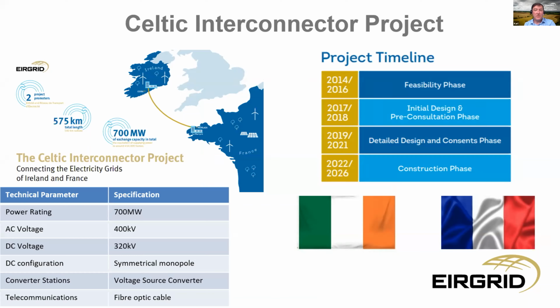The specification of the project is similar to that of EWIC. It will be a VSC converter with newer technology. It will have higher capacity of 700 megawatts. The cable voltage will be 320 kV and will have a fiber connection. RTE is the largest TSO in Europe, and it is really great and interesting to work with their teams. Our engineering challenges are very, very similar.